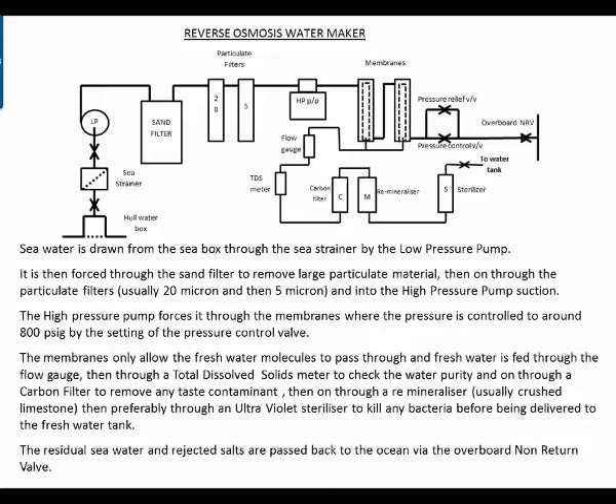The high pressure pump forces water through the membranes where the pressure is controlled to around 800 pounds per square inch by the setting of the pressure control valve. The membranes only allow fresh water molecules to pass through, and the fresh water is fed to the flow gauge, then through a total dissolved solids meter to check the purity of the water.